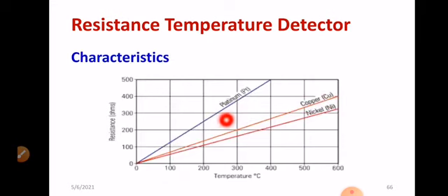So this is another graph. It also shows the wide temperature measurement range of platinum. So platinum is much preferable. How do you measure the resistance? For example, you are using platinum wire. At 400 degrees Celsius, you just calculate the value of resistance. Resistance will be almost 500 ohm. Okay, that means at 400 degrees Celsius. Suppose you are measuring the resistance of the platinum wire at 400 degrees Celsius, the resistance must be 500 ohm. For example, at 200 degrees Celsius, the resistance will be in between 200 and 300, say 250. You can look here at 200. See, at 200 degrees Celsius, the resistance will be 250 ohm. Likewise, you are able to measure.